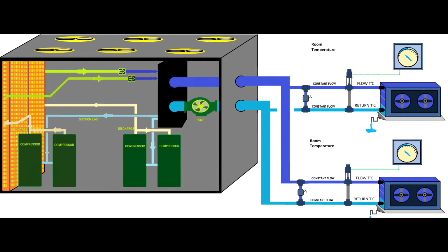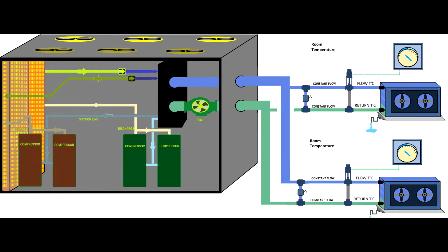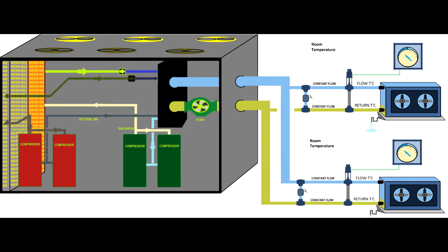If the cooling glycol gets hot, then you have to go and look into the chiller. Maybe two of the compressors are off, maybe all the compressors will be off, maybe you have some faults in the refrigeration system which is not allowing the refrigeration group to cool the cooling agent. Then the cooling agent will lose the property. You will have an increase in the glycol flow temperature. And if you have that increase, the actuators which control the flow onto the heat exchanger will open 100% because they will be starved of capacity.